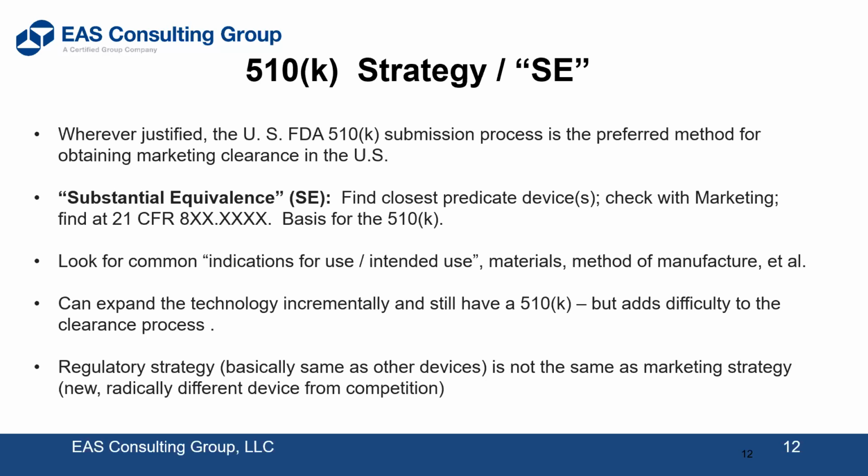And so the same goes for intended use. In the past, those indications for use were not highlighted. They might have been mentioned in a general narrative, and they're hard to find. But that's not true today. One of the tabs is specifically dealing with indications for use. So the FDA has steadily tightened up the definitions of the various requirements that go into a 510K. Now, the second from the bottom bullet point is a point that we're really stressing in this discussion today. You can expand the technology incrementally and still have a 510K.